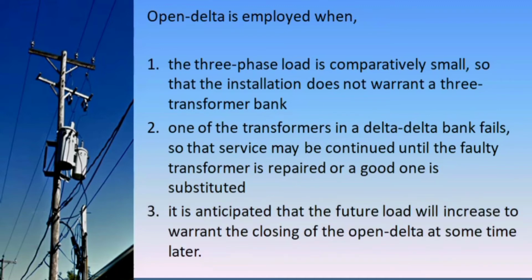And number 3, open delta is employed when it is anticipated that the future load will increase to warrant the closing of the open delta at some time later. Again, it's clear that when expansion is needed for future loads and there's a need for a closed delta system, then open delta is used for the meantime.